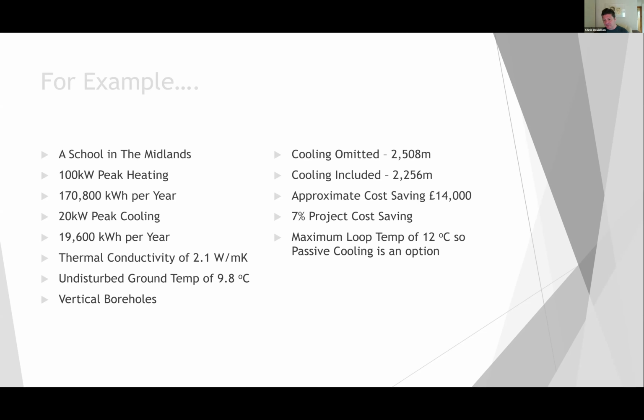On this model, we've run the loop temperature, so I'm going to show you some graphs in a second, and the maximum loop temperature gets up to about 12 degrees C. So in this instance, we do have the opportunity to do some passive cooling, provided we can design around a temperature of about 12 degrees C in those cooling circuits.